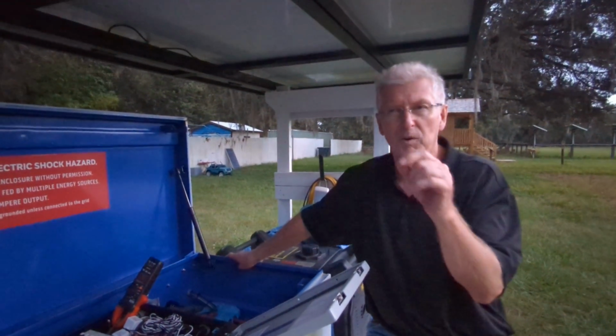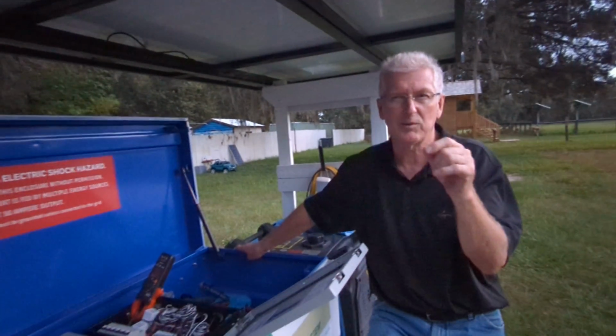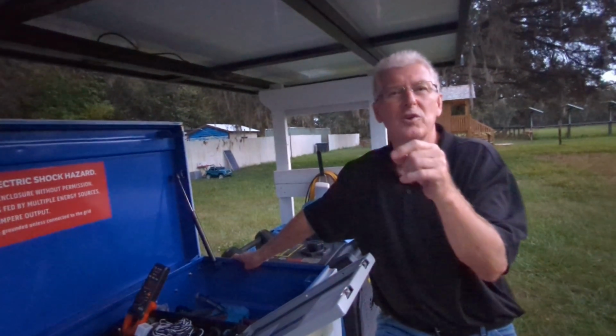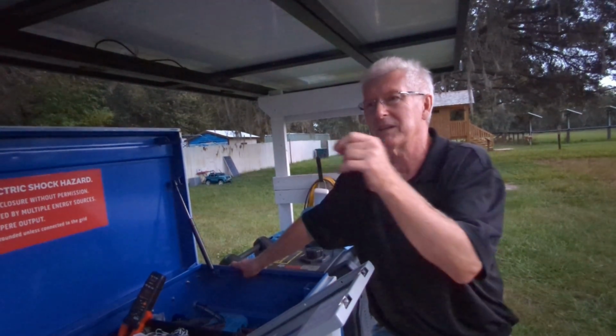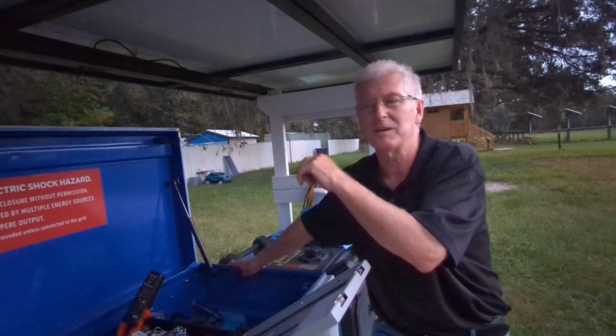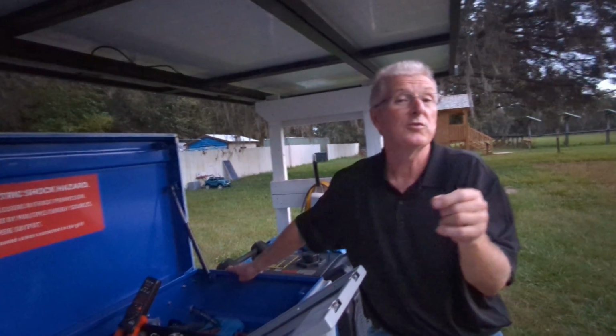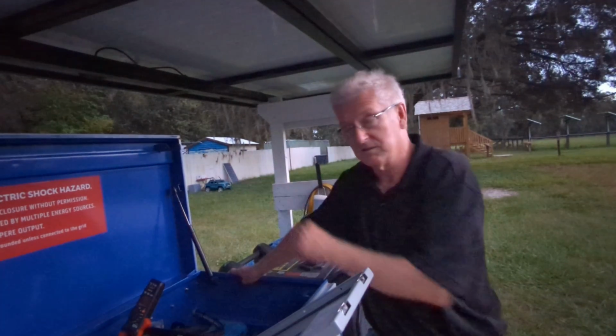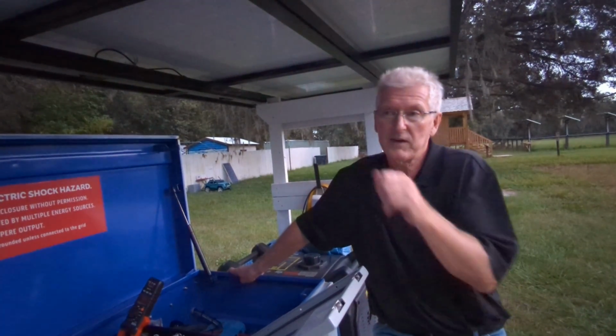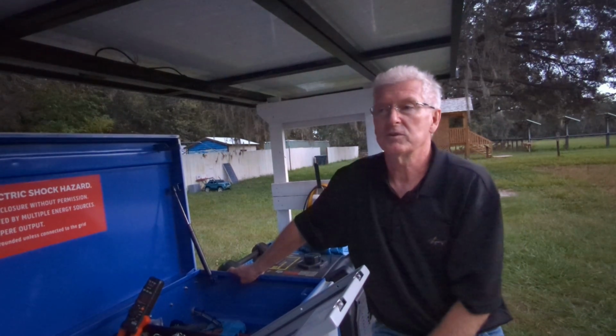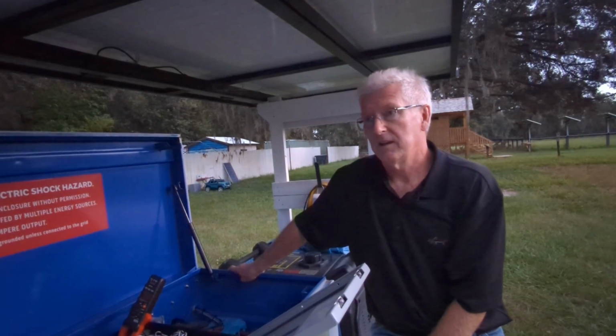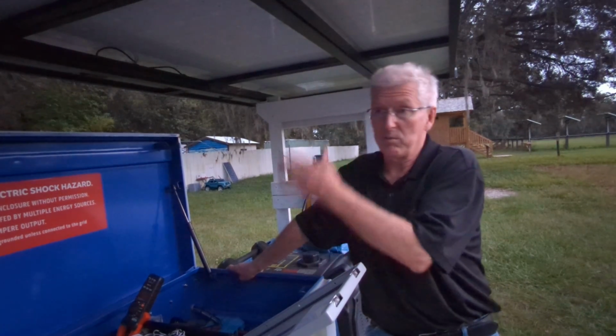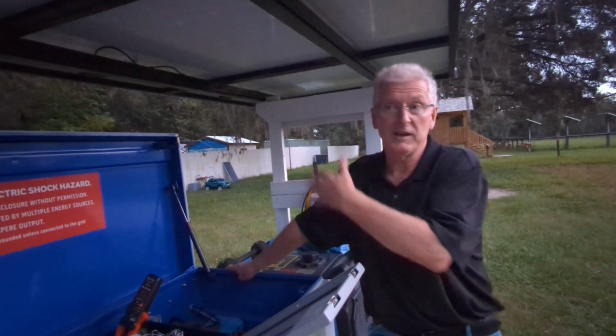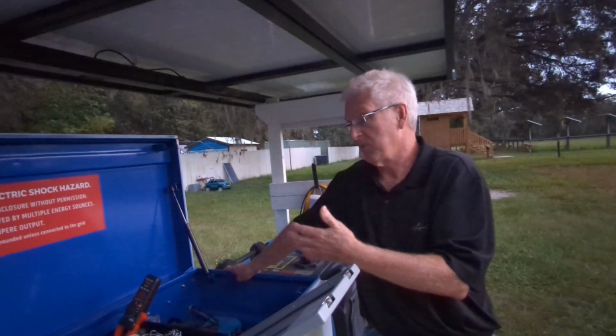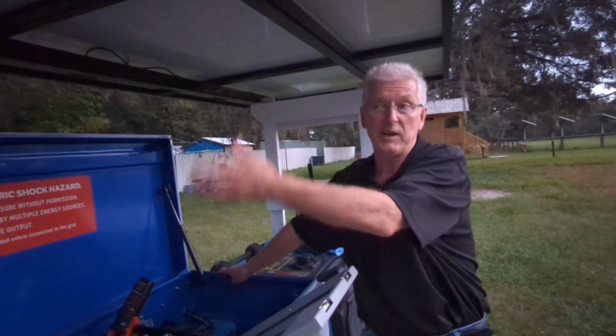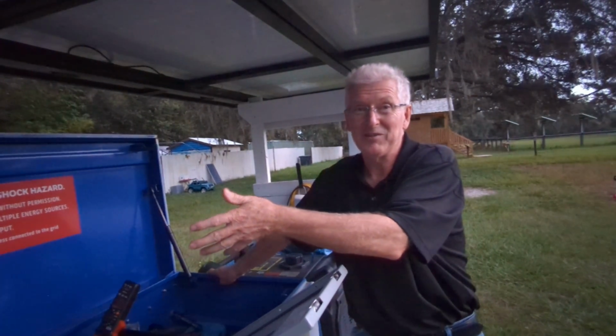Okay. Now there might have been some other small loads in there, like the lights, which are 0.5 kilowatt maybe or less. And then the converter. And the converter, which was putting in 2.6 amps. 2.6 amps, something like that. But that's not very many kilowatts, right? 2.6 amps times 120 volts. Could be. But it was on both legs. Oh, it was on both legs, so it's 240 times that. 3.6. So now we've got some data that you can start to crunch some numbers, and you can see that with the generator running, you can power both your ACs because it's got no problem handling the 3.5. Right. In fact, it was providing the 3.5 to the two ACs, and it was providing one to charge the batteries. Right. So it was providing 4.5.